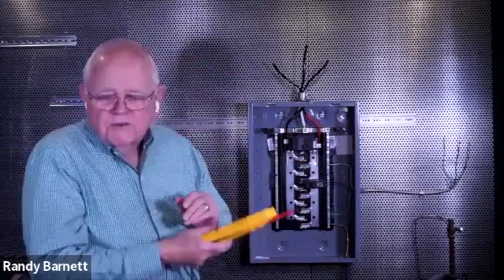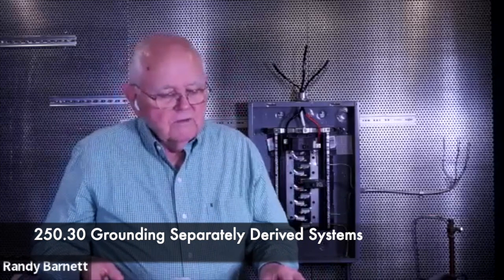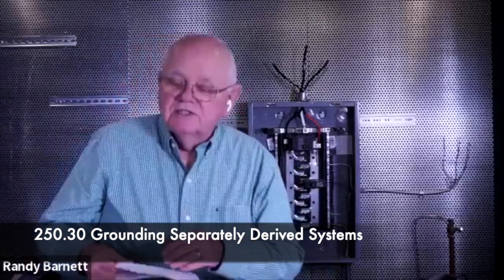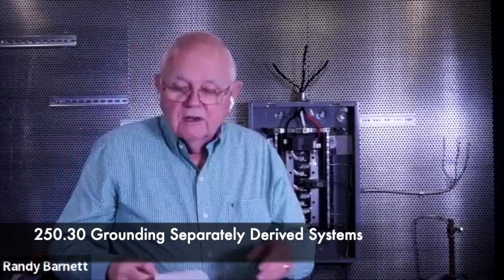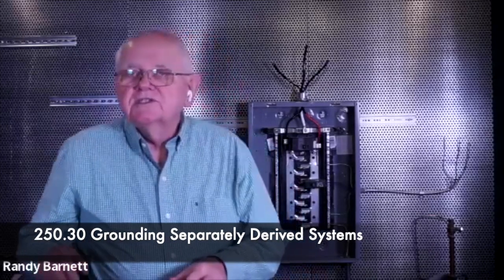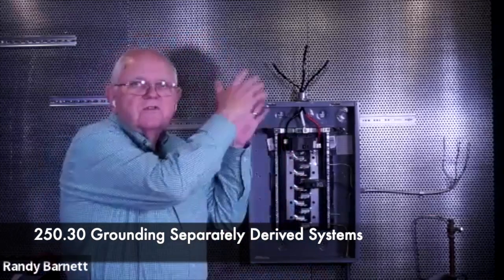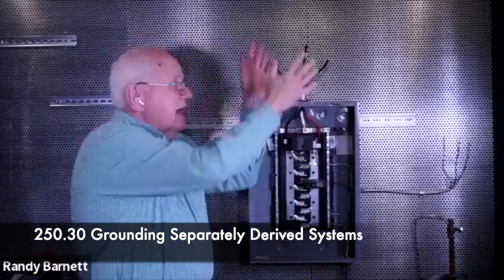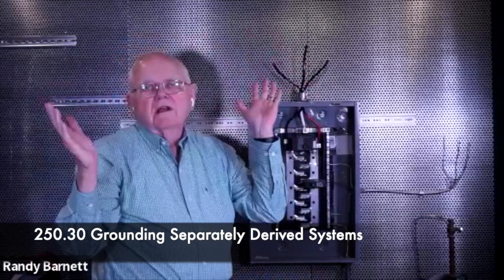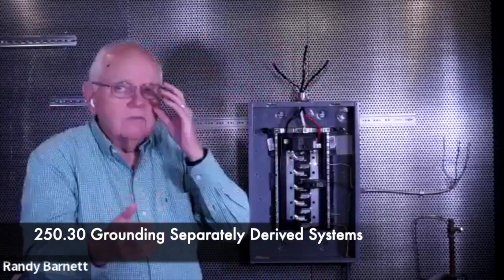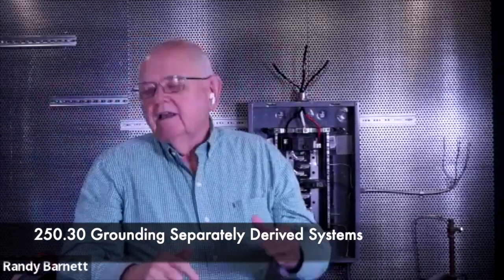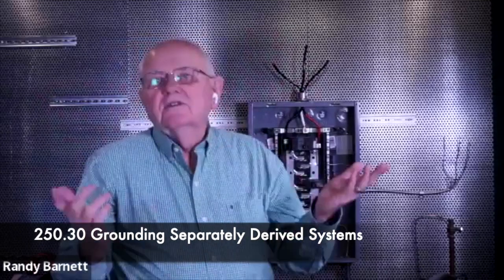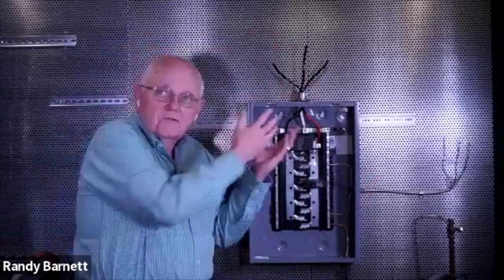And then finally, 250.30 talks about separately derived systems. The difference, go back to your Article 100 definitions. Basically, if we come from the utility, it's a service. If power comes in from the utility, it's a service. If it comes from our transformer on site, which is, of course, very common, then we refer to it as a separately derived system. Why? Because we're deriving the power separately from our own transformer for our system.